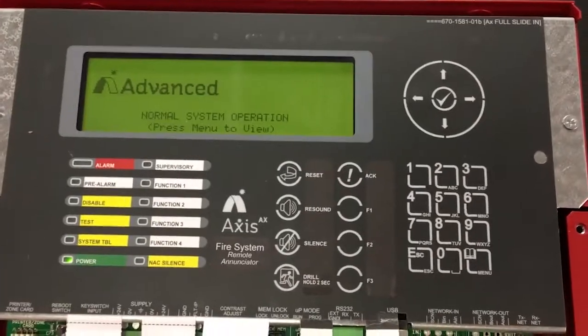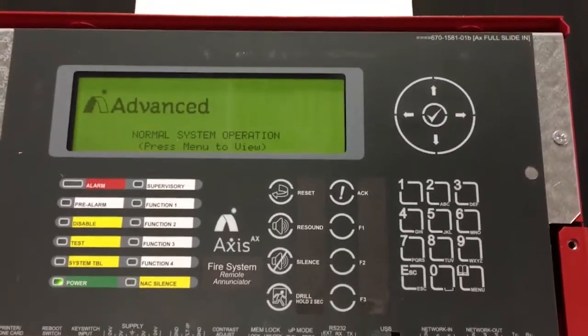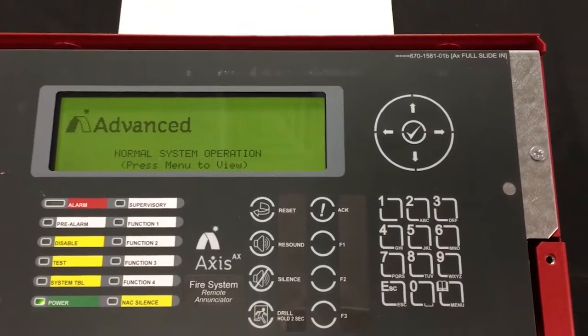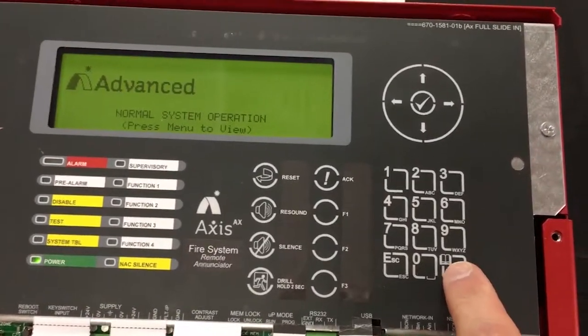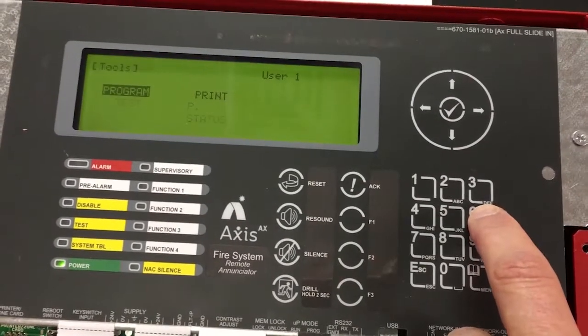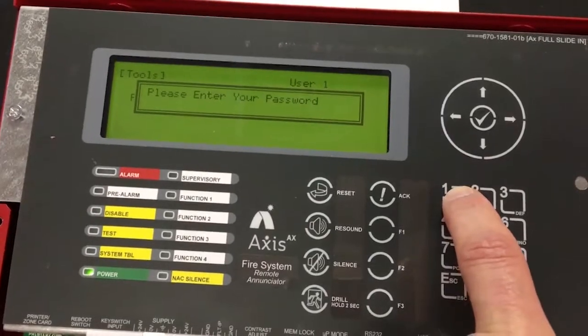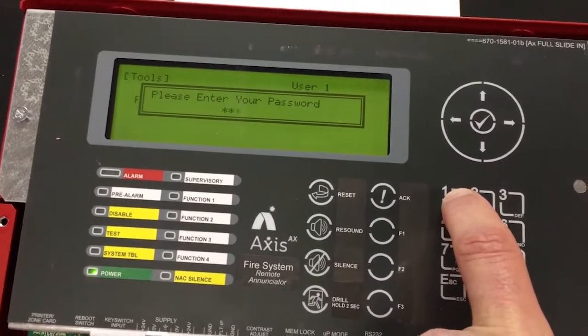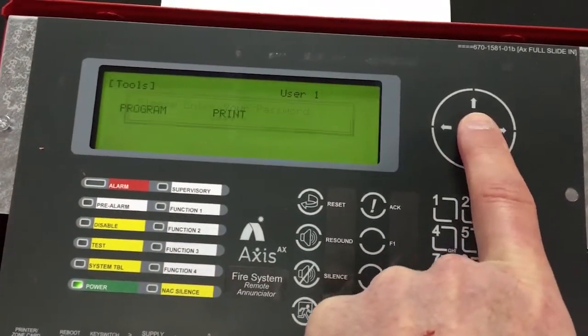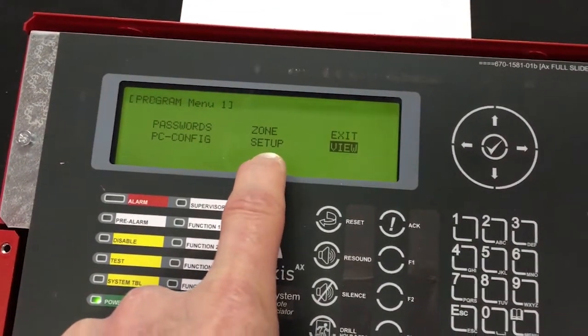The next thing we're going to do is come to the annunciator, and we have to do something very similar. Again, we're going to hit the menu button and get into programming — six for tools, one to program. My password is 1111, followed by the check mark. Once I'm in, we're going to look for the setup screen, same location. We'll scroll over to setup and hit the check mark.